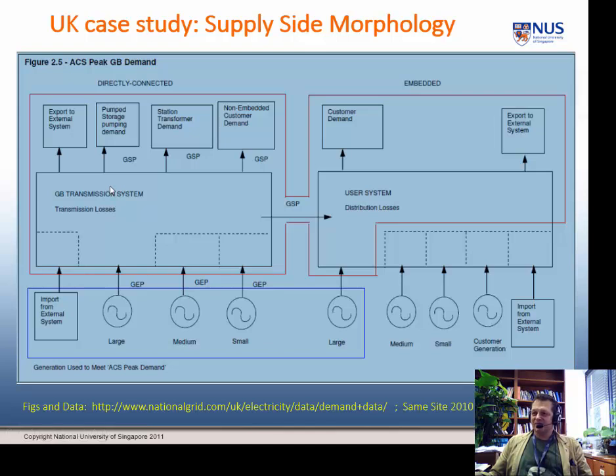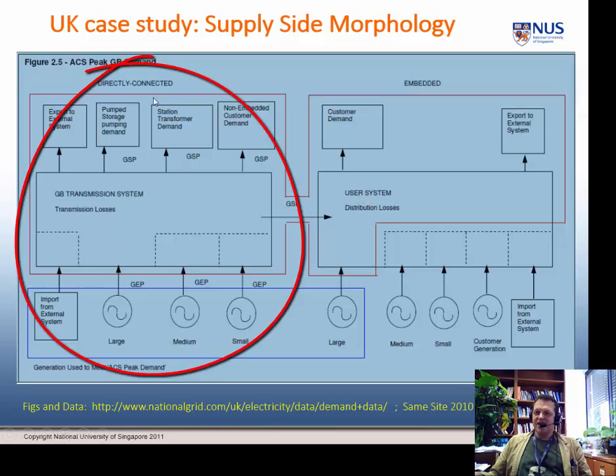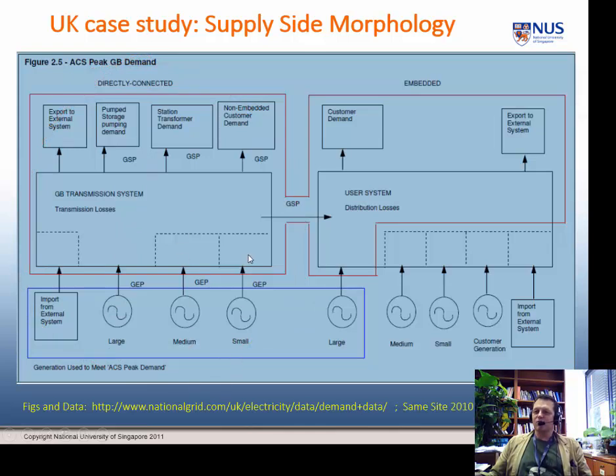Now, there are embedded parts to this, and there are directly connected parts. So typically, the automatic load shedding we were talking about would be an example of embedded. Okay, so here is our transmission system. So we have large power stations, medium power stations, and small power stations, which are pushing straight into the national grid system. You have import from external systems, so that's DC grids, high voltage DC links, for instance. So that's the grid, and that's exported to directly connected systems like pump storage.